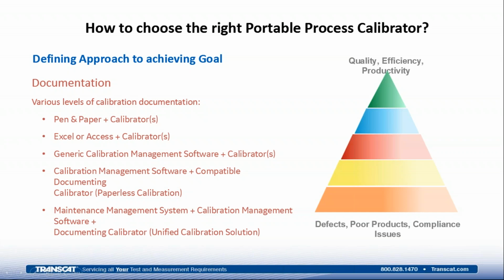So there's different levels of documentation that we can do or look at. The first one is the old reliable pen and paper with the calibrator. Stepping up from there, we can use an Excel spreadsheet or Access database plus the calibrator. Then we move into software where we have just a generic calibration software where we can effectively facilitate moving calibrations from the calibrator directly into a software program.